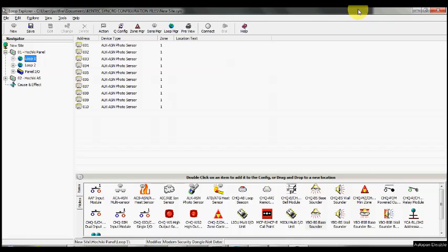So where would we use the first and second stage delay? Well, one area might be where we have a site that doesn't want to evacuate the whole site on a single smoke detector. They would like to have an acknowledgement period, maybe up to 30 seconds, so that when a smoke detector goes into fire, the beacons operate immediately but the sound is delayed for 30 seconds for someone to go to the panel and acknowledge the system by pressing the acknowledgement button.